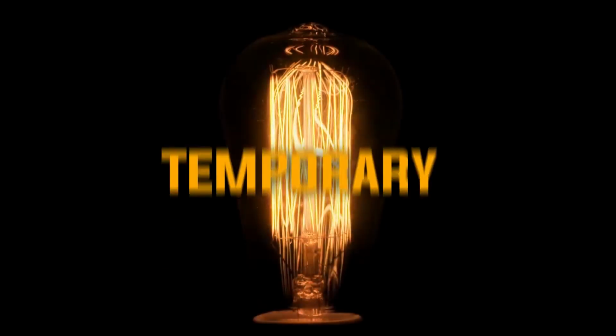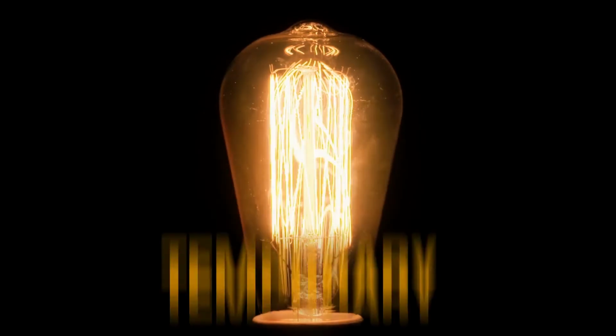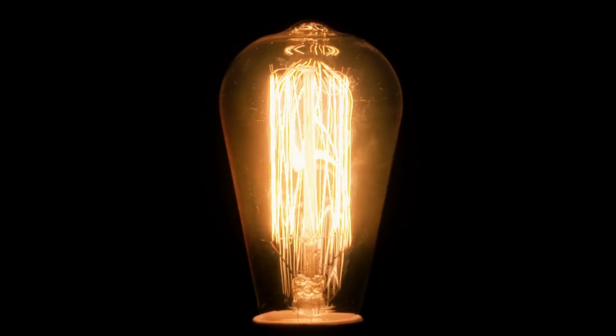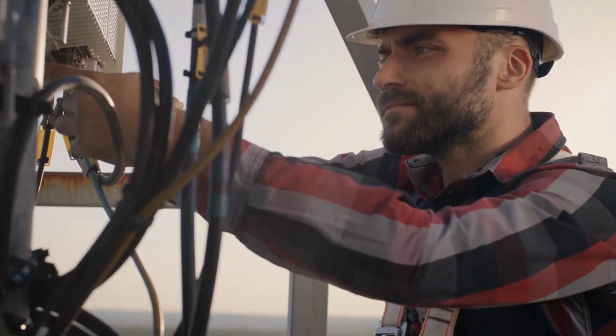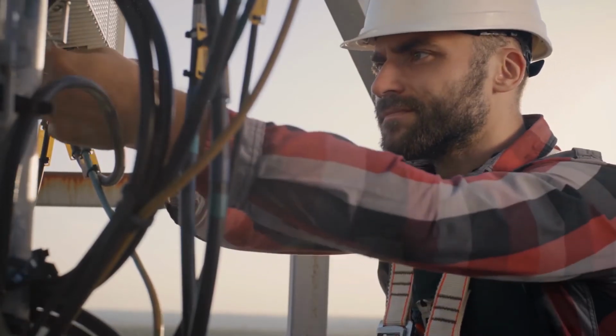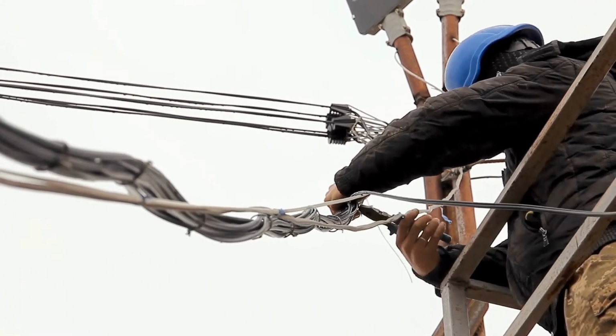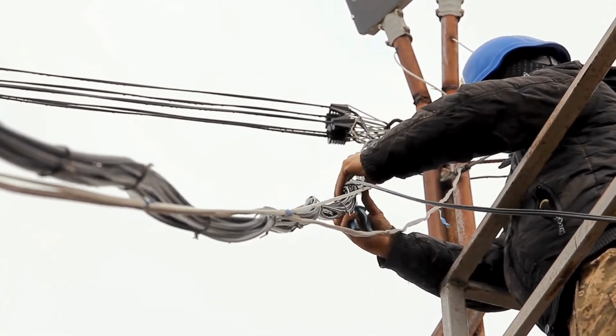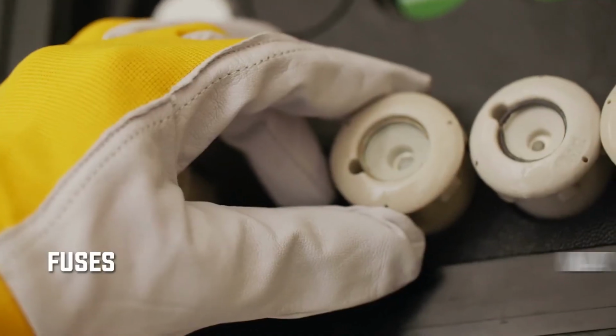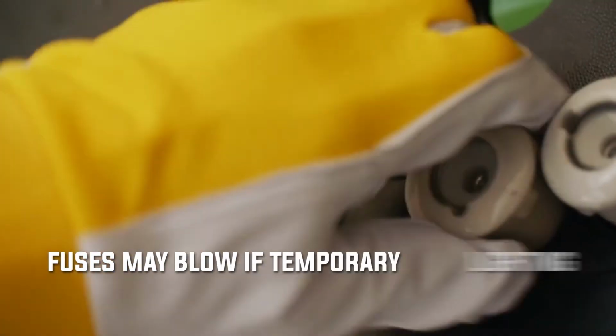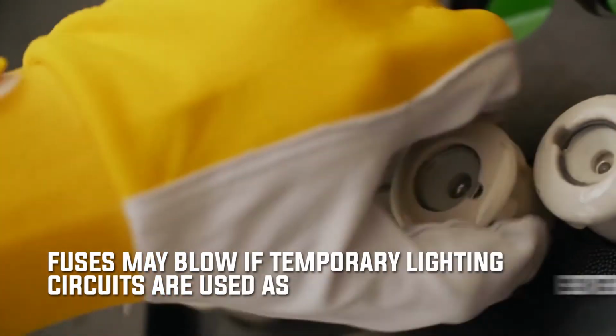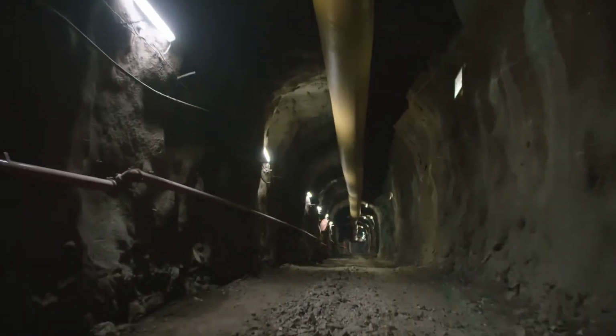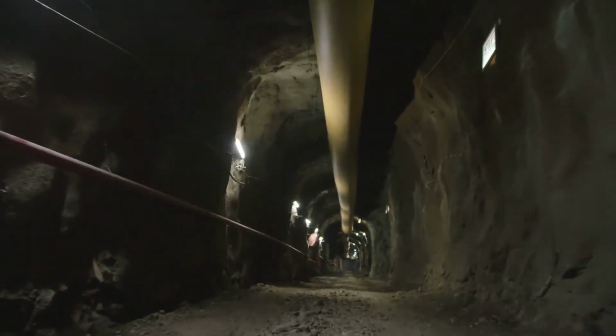The following are the temporary lighting hazards. Electricians have been electrocuted while setting up temporary lighting. The frequent relocation of circuits can loosen connections, break insulation, and create other hazards which may lead to shock or electrocution. Fuses may blow if temporary lighting circuits are used as extension cords, and that can be dangerous when finding a way to the panel in the dark.